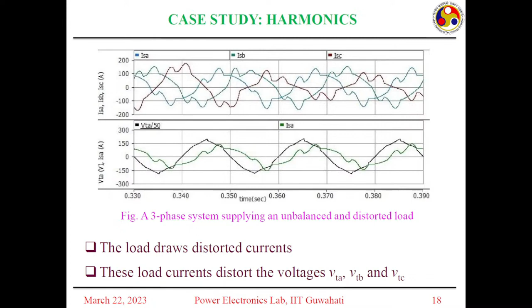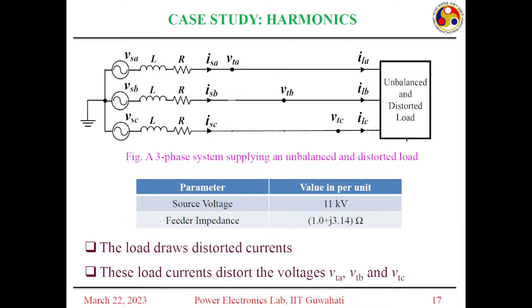Now this is some customer. Some customer 1 has connected this load. Let us say I have a customer having only a linear load, only some RL load. If I want to connect at the same bus, I will also get the distorted supply. So I am not polluting the supply, I am connecting a linear load only. But because of some other customer, my load is also affected. Okay, so this is the case study of harmonics.